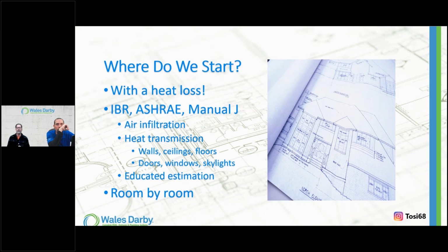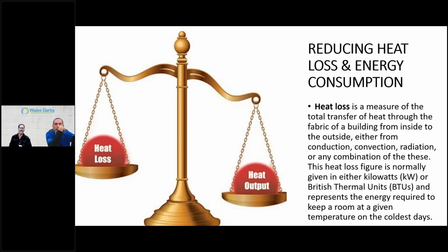Like, well, let's start playing with lowering water temperature. With non-condensing pieces of equipment, cast iron, we have a threshold no lower than 140. I don't want to condense in a non-condensing piece of equipment, all right? But 180 to 140, if I'm just pegging the 180 all the time and I'm wasting fuel and it's leaving the building and not going into my pocket or my comfort, right? That's a waste. So the idea is, wow, if my emitters have more surface area than needed, let's look at a chart, and it tells me how many BTUs per foot with 140.